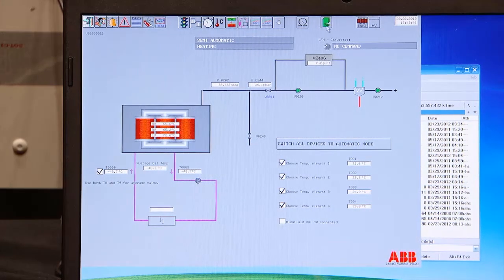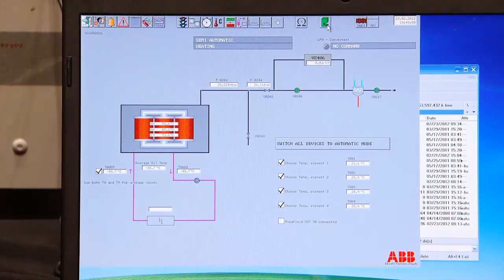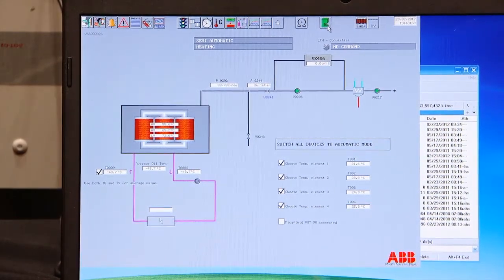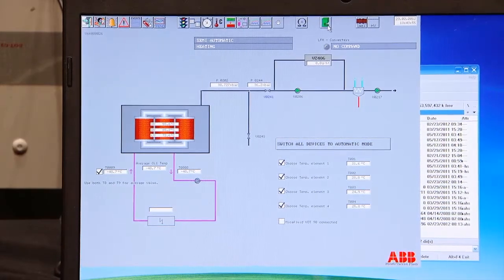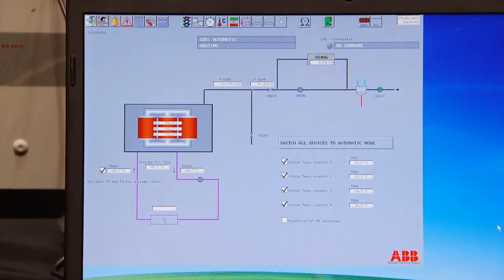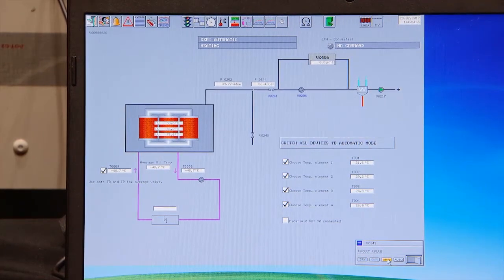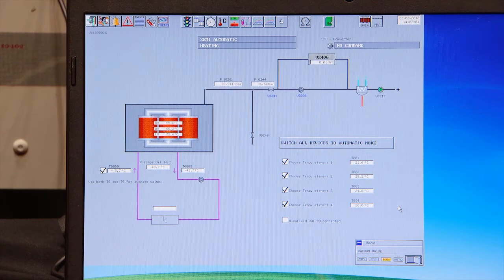So go to the page, the green box. The former generation of this VZ406 was green. Now it will change the color to red. Okay, we will now do the suction capacity measurement for the vacuum pumps. We make sure that our main vacuum valve is closed. Coming from automatic, put it in manual and keep it closed like that. In that way we will make sure that it's not opening, it's not halfway open, it will go to fully closed.